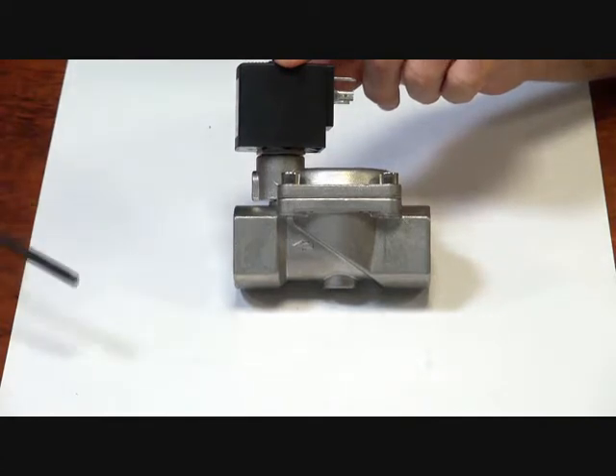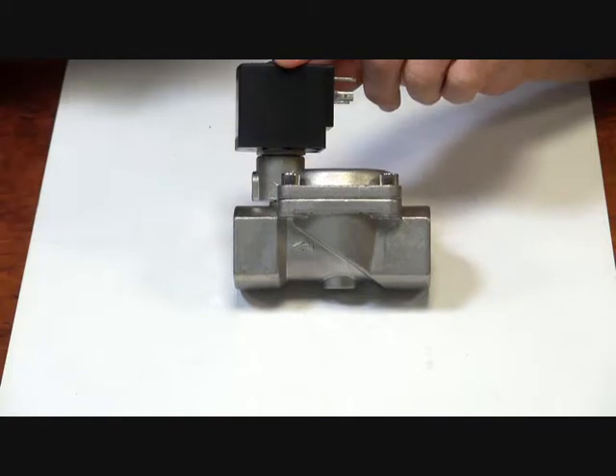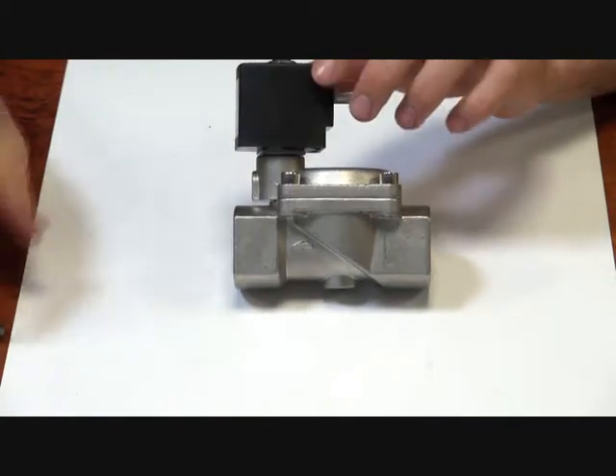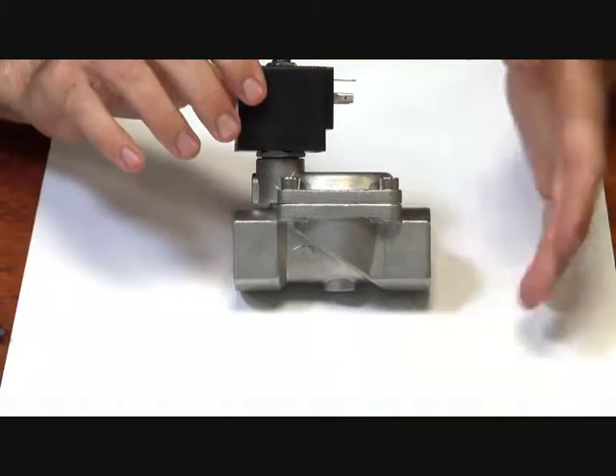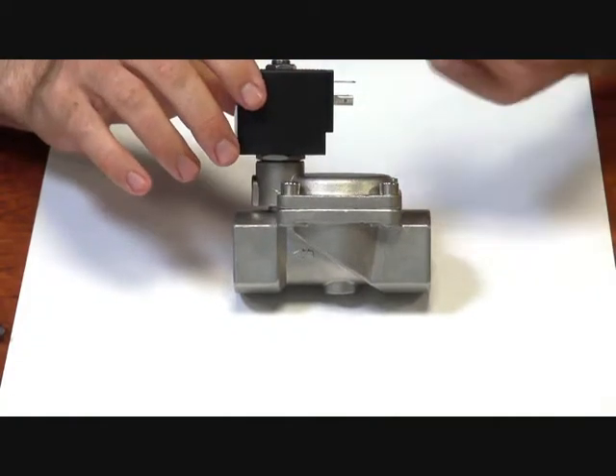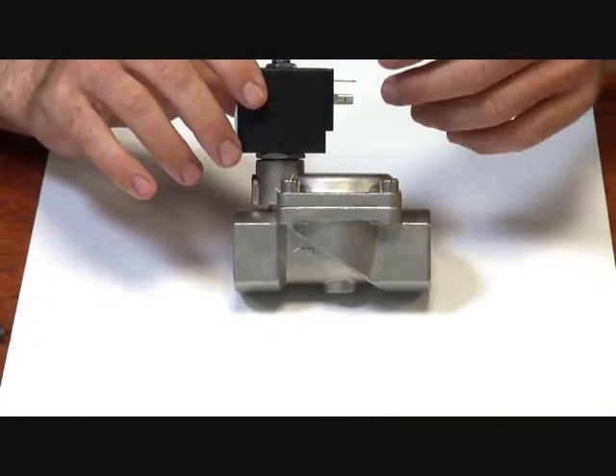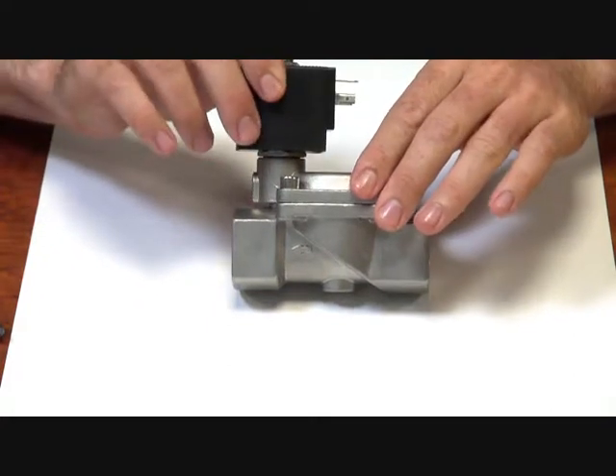So where's it's good? Well, it's good in applications such as mains water, downstream of a pump, compressed air lines. So this valve here, it's got an EPDM diaphragm, so it's good for water, compressed air, any sort of inert chemicals, or inert media, I should say.